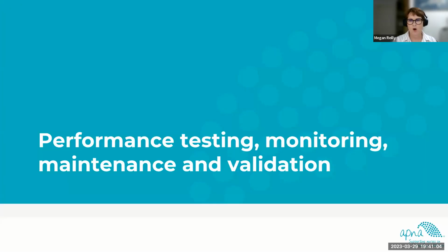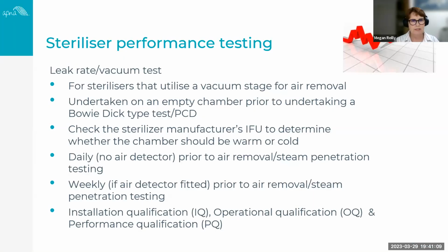Okay, and moving right along, performance testing, monitoring, maintenance and validations. I'm not going to go into significant detail. This is a whole topic on its own. The RACGP IPC guidelines cover this really well. But suffice to say that your sterilizer, in fact, all of your equipment, but for most of you, it's probably the sterilizer that is the automated process in your reprocessing area, the sterilizer needs to undergo performance testing, and that will depend on the type of sterilizer.